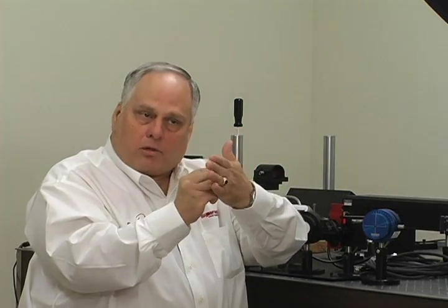And if you have a high power in a very tiny space, that's the size of your laser. If we put too much power in a tiny space and you stick it directly on your sensor, you're going to blow a hole in it. Do you need to attenuate your beam or not? And what sort of attenuation do you need? That also factors in with the wavelength because different types of attenuation schemes are only applicable to different types of lasers and wavelengths.